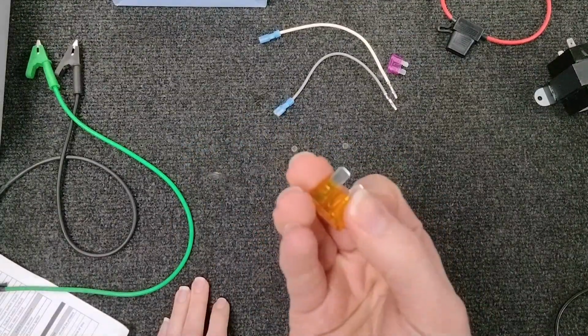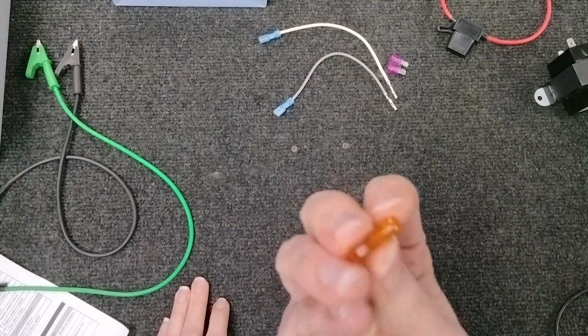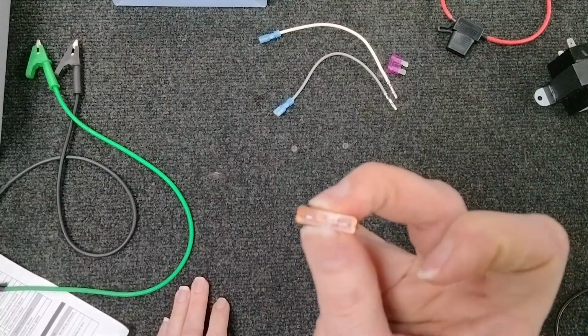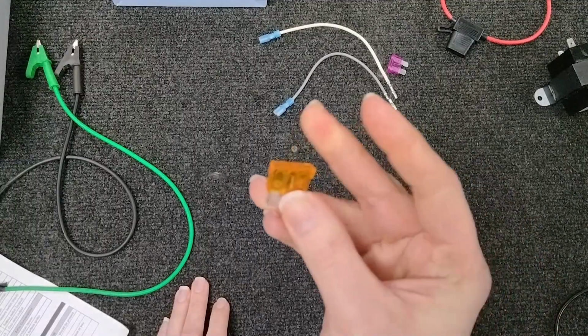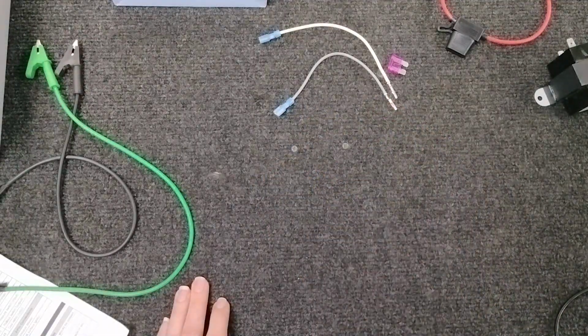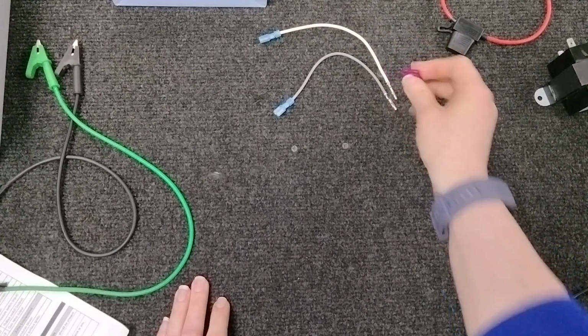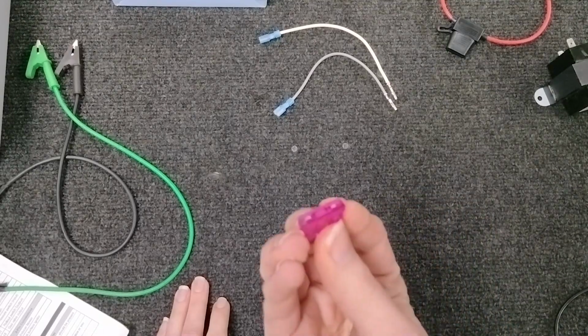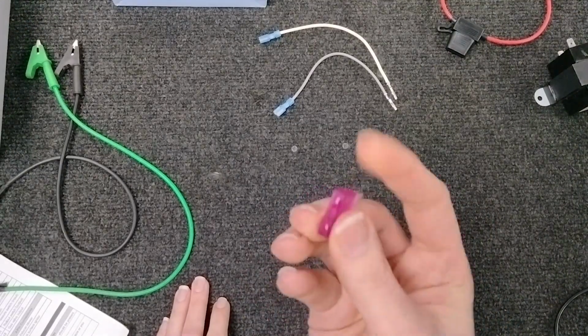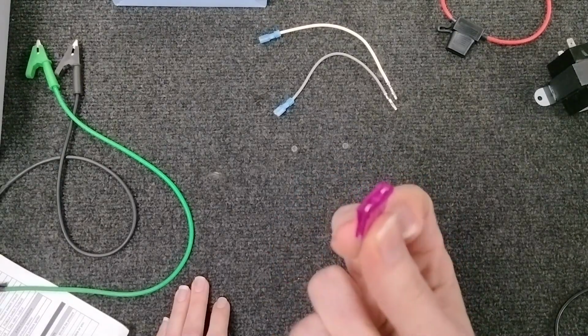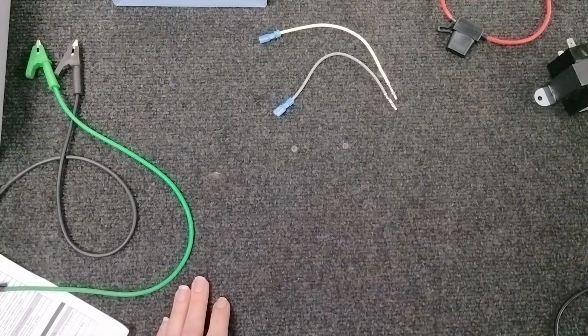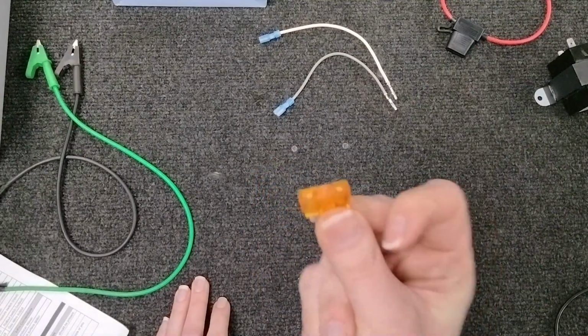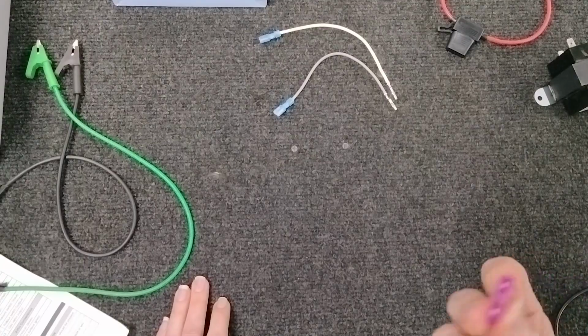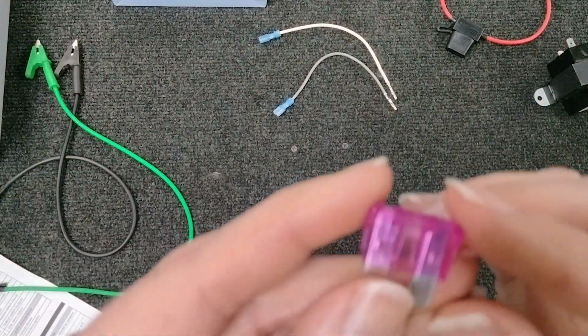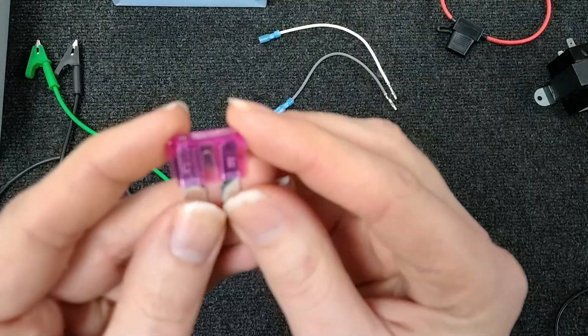If you see a higher fuse in there than a 5 or a 3, that is not going to catch that low voltage short, and it will take out your board and your transformer. Automotive fuses are higher, and they're not suitable for your HVAC units. So always make sure that you have no more than a 5-amp fuse in there, and most units, their control boards use a 3.